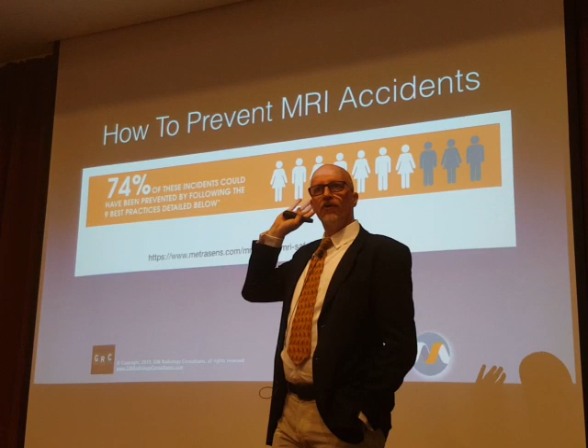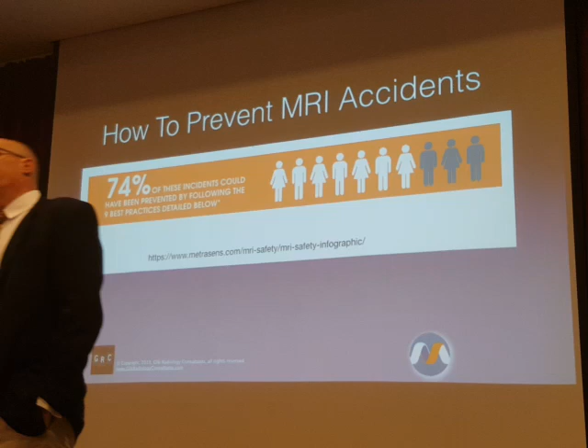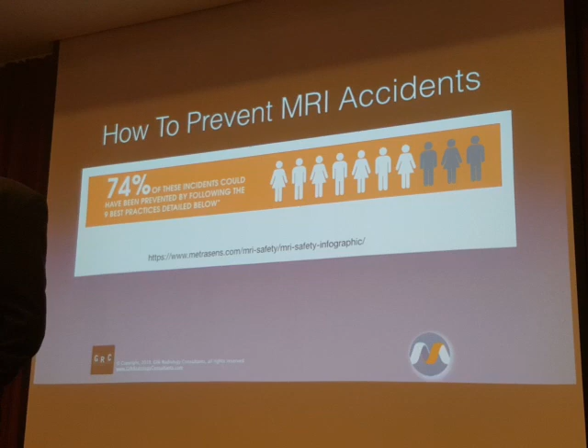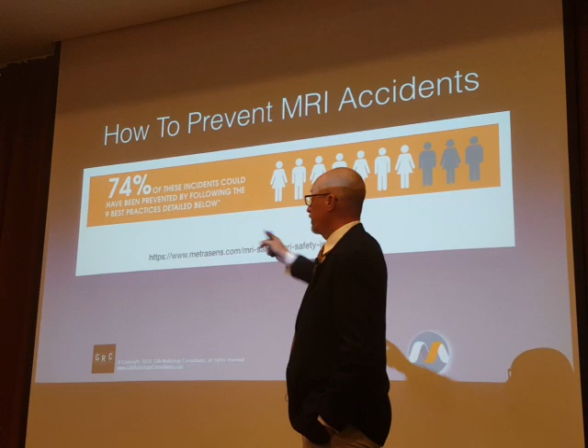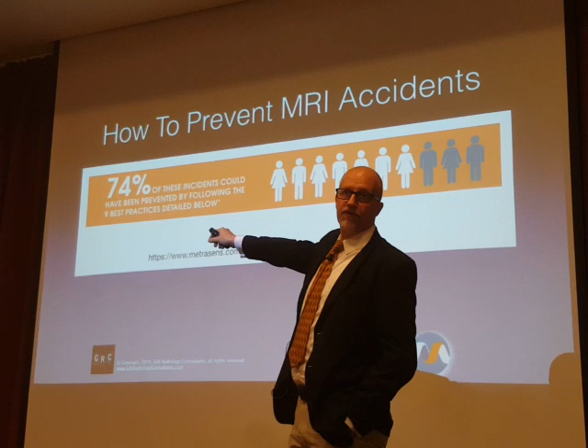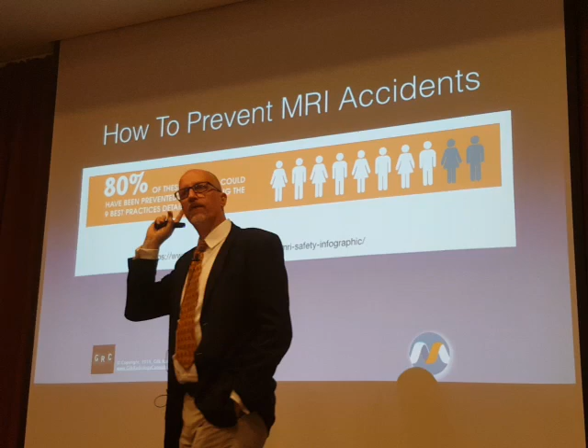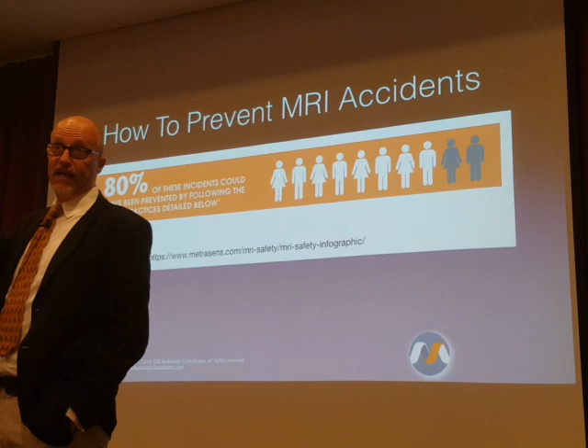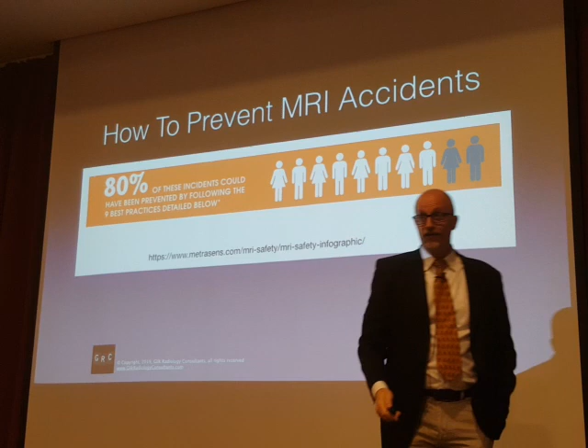And then the 3 protections for projectile-related injuries. The three that I identified for radio frequency burns, the three that I identified for projectiles, and the one for hearing damage, those are all existing best practice statements from the ACR guidance document. Those taken together would have stopped 74% of the injury accidents. And if we exclude the service personnel from that, that 74% jumps to 80% in terms of the percentage of injury reduction that we can do.